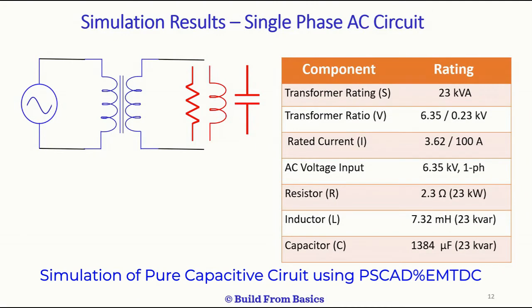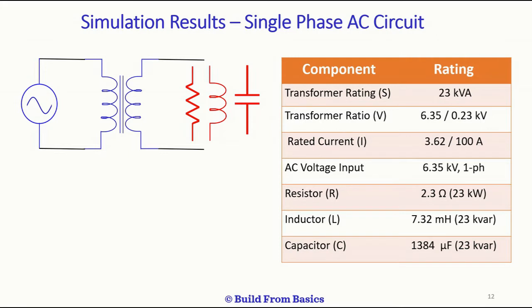Let's take a single-phase supply of 11 kV line voltage, giving a phase voltage of 6.35 kV. We take a transformer of 23 kVA with a ratio of 6.35 kV on the primary and 230 V on the secondary. The rated current in the primary is then 3.62 amperes and in the secondary is 100 amperes. Now let's calculate the resistor, inductor, and capacitor values using the relevant formulas.